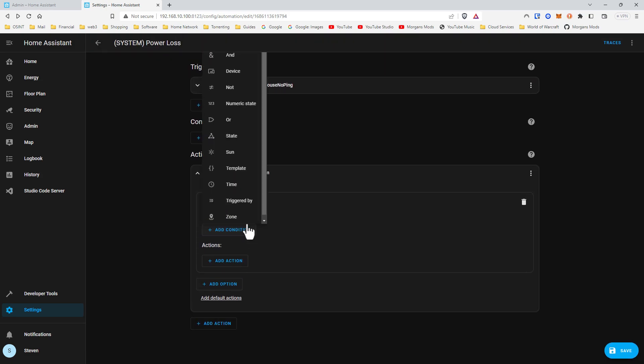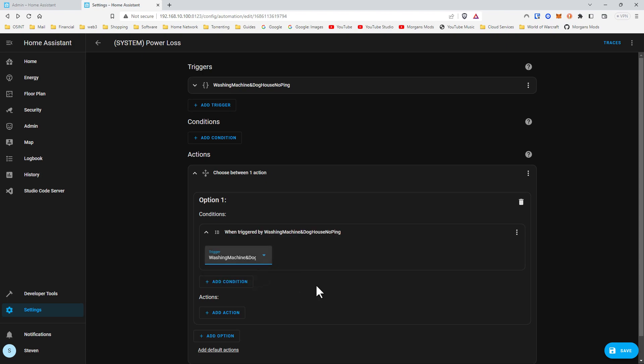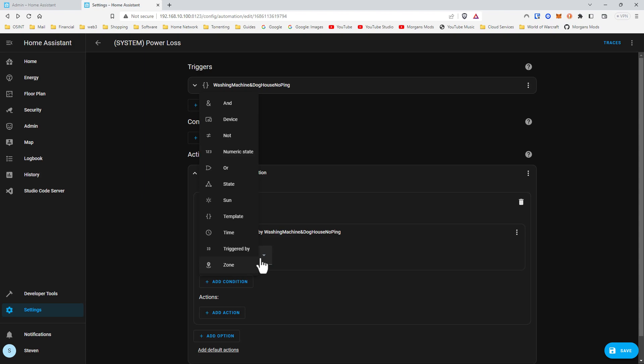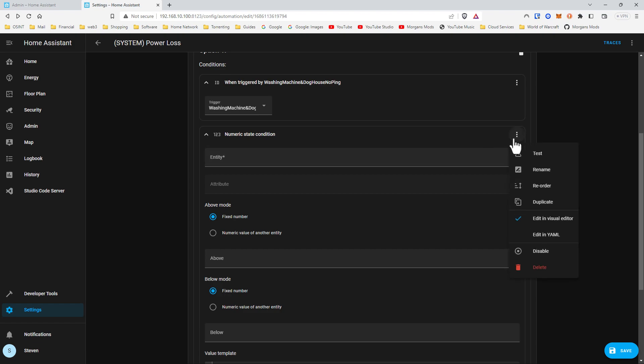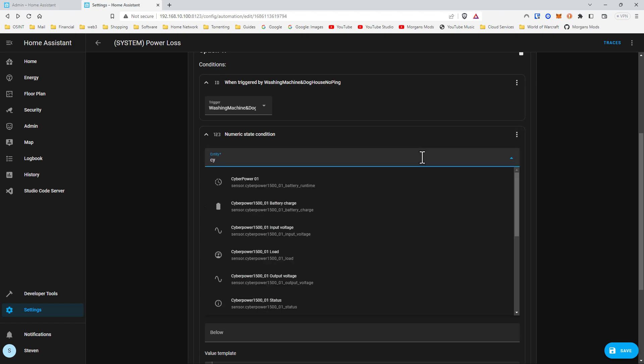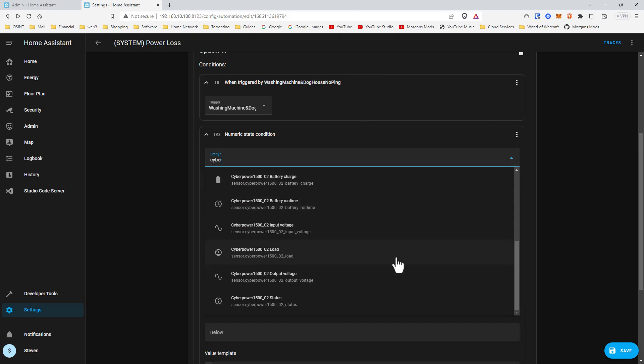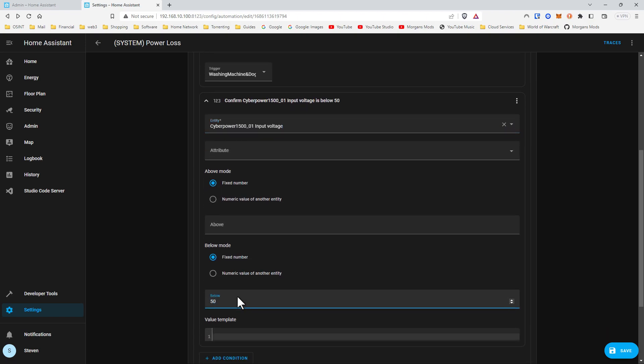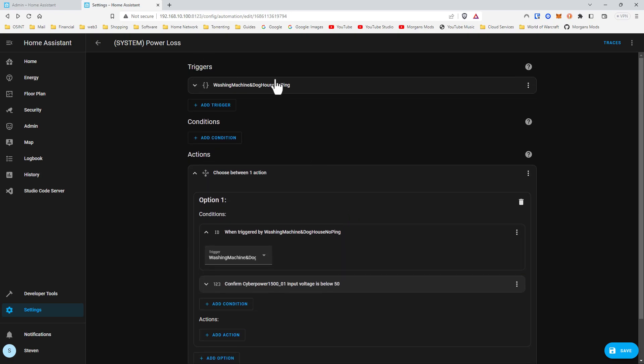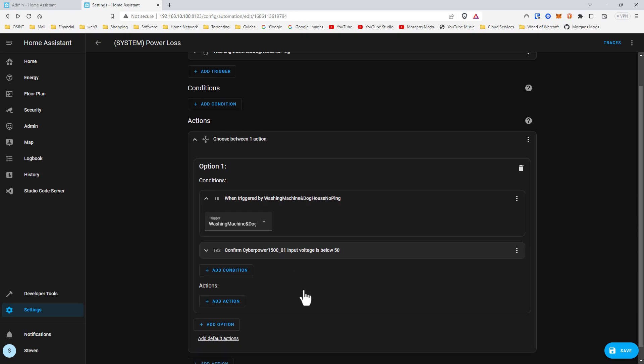We're gonna hit choose. Now we're going to be triggered by this — if there's no ping and the numeric state of the UPS is below 50. Because these are the UPSs, they will maintain power even if there's no input voltage. So if this is below 50 and neither one of these ping — and they're both on separate phases of the utility power coming in, one's on an even breaker, one's on an odd breaker — if neither one of those are pinging, confirm that the input voltage on the UPS is below 50, which it will still be able to report because the internet still works.